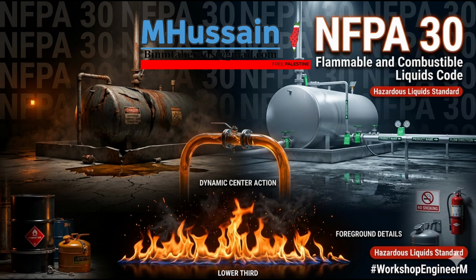The mechanics of that blanket are brilliant. It attacks the fire on three fronts. First, the water in the foam provides cooling. Second, the physical mass of the foam acts as a barrier, floating on the hydrocarbon and cutting off the atmospheric oxygen. And the third front is vapor suppression, which is probably the most vital. Right. The aqueous film actually seals the surface of the liquid, physically preventing more ignitable vapors from off-gassing and feeding the thermal column. By choking off the vapor, you choke off the fire.